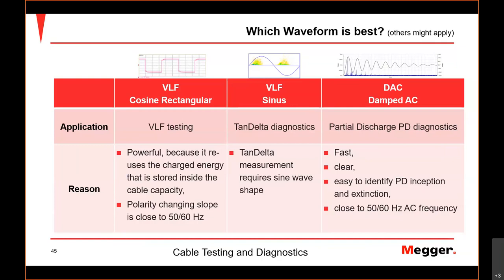But the voltage shape in general should be applied for 1 hour, because these electrical trees still need many minutes, up to 60 minutes, to grow from becoming a bit critical to really a fault that you can locate and repair the cable. So you should wait for 60 minutes.